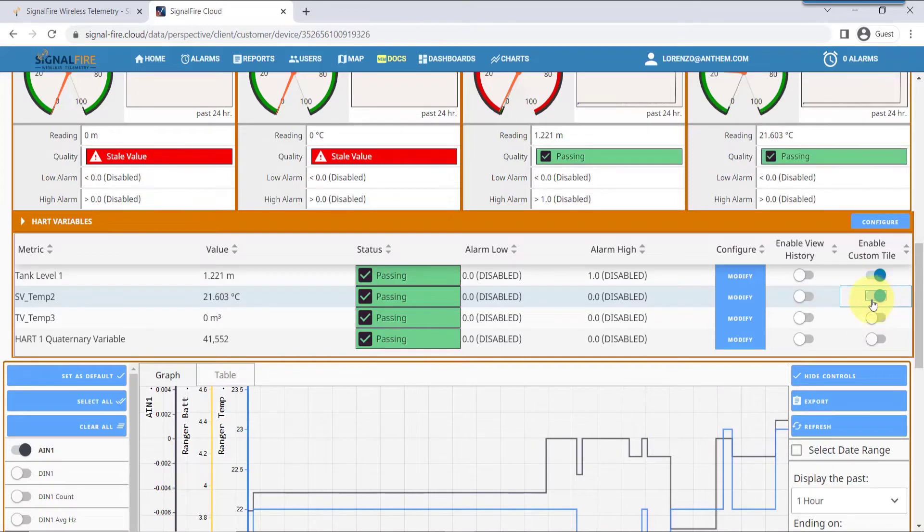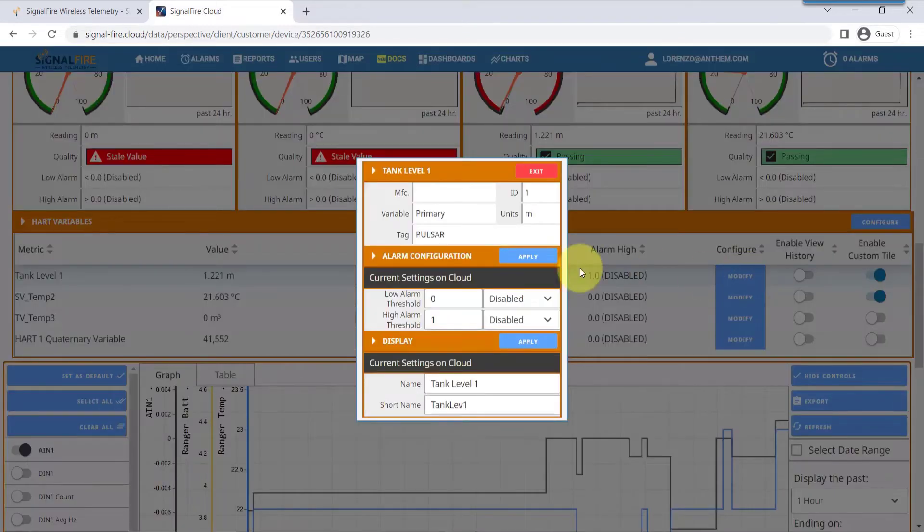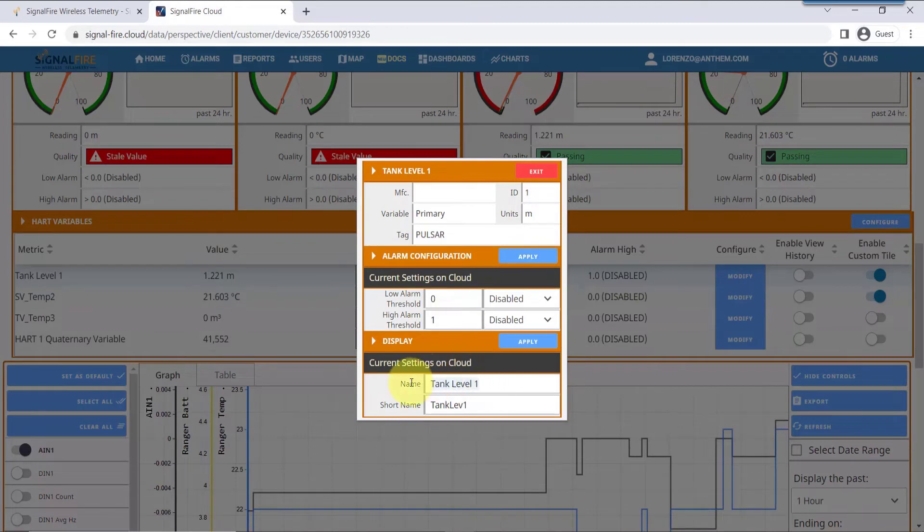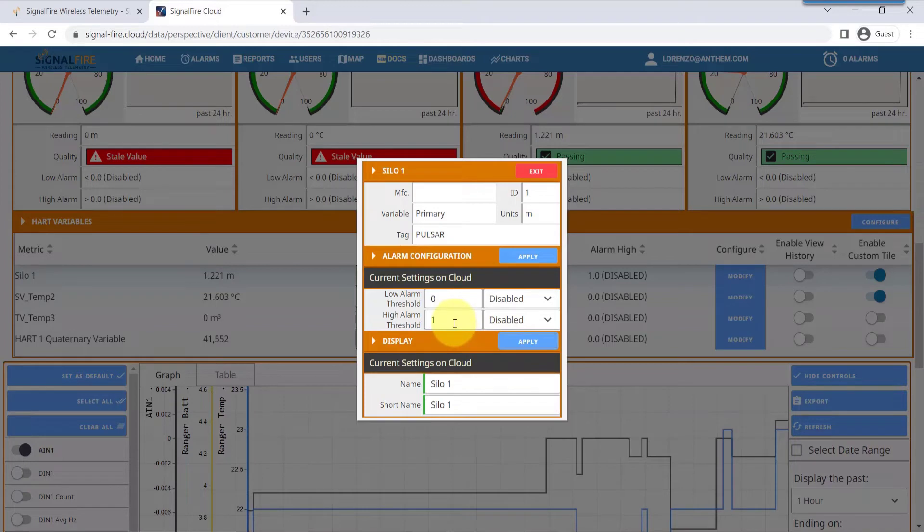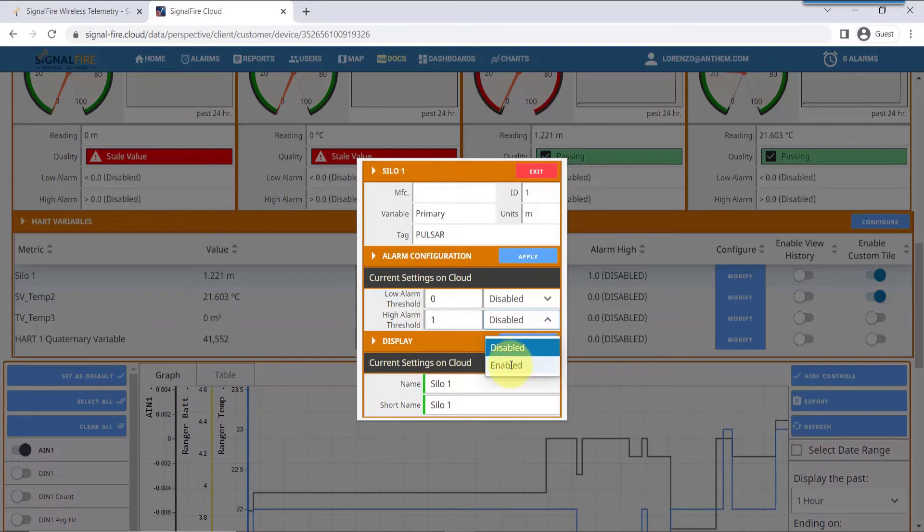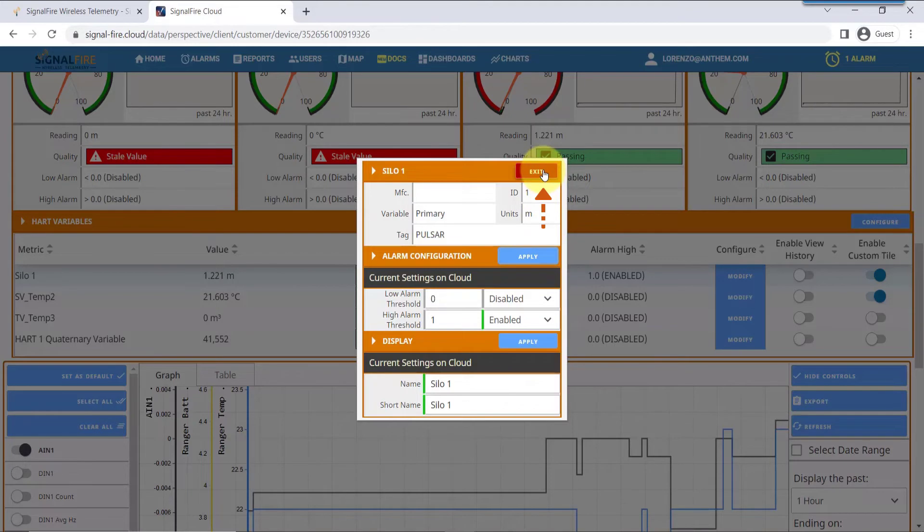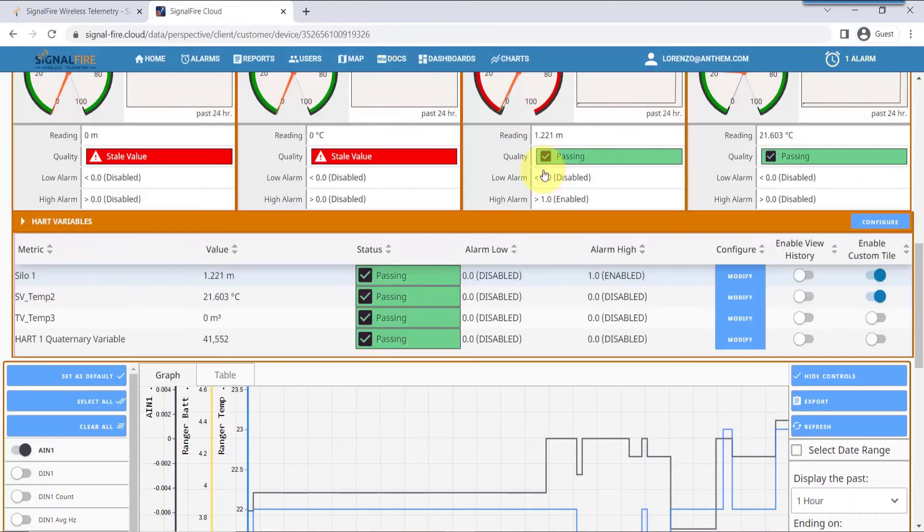You can elect to have each of these variables set as tiles by clicking the Enable Tile function and also put a useful name to that HART variable. In this case, I'll put Silo 1. Hit apply. You can also set alarms if you want to have a text message, an email, or the web app to indicate an alarm by activating the alarm and setting a threshold for it.